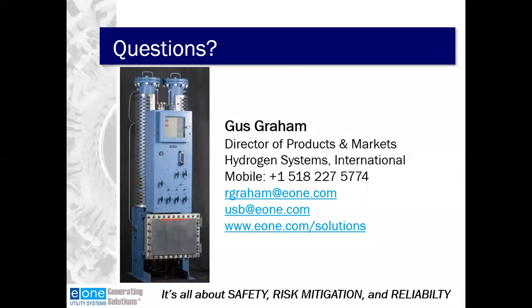Very good. If the inlet gas dew point is low enough, will the dryer go on standby? So the dryer just will not perform a regeneration. We'll monitor the dew point, and if it's stable and below the set point, we will only perform a regeneration based on a time, and that's to ensure that the actuator cycles and that the columns are balanced for usage.